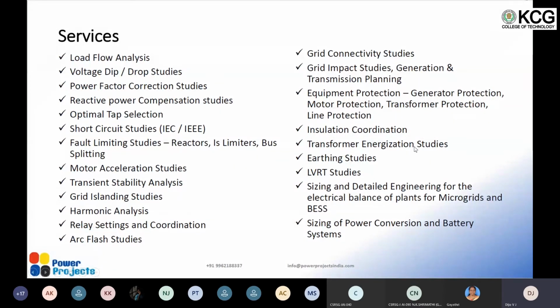Transformer energizing studies we do. Like if the largest transformer is to be energized from a weak source, this is a very critical study, as there may be an issue on energizing the transformer on a weak system. So we do such studies. We do earthing studies. We do low voltage ride through studies. Then we do the sizing of electrical equipment, maybe detailed engineering for the electrical balance of plant, microgrids and battery energy storage systems, sizing of power conversion and battery systems.